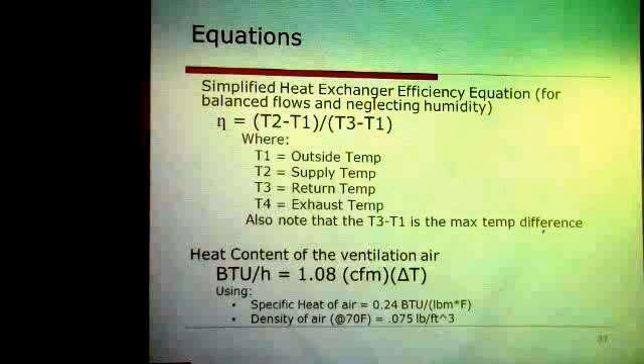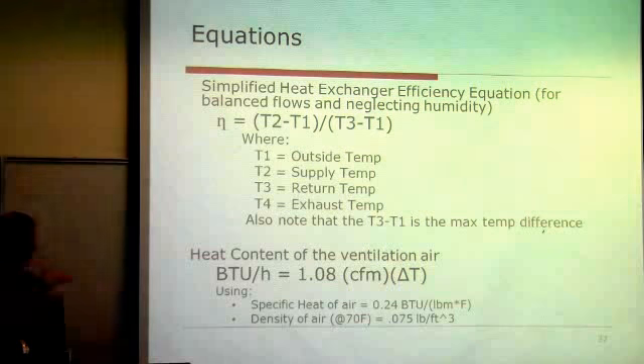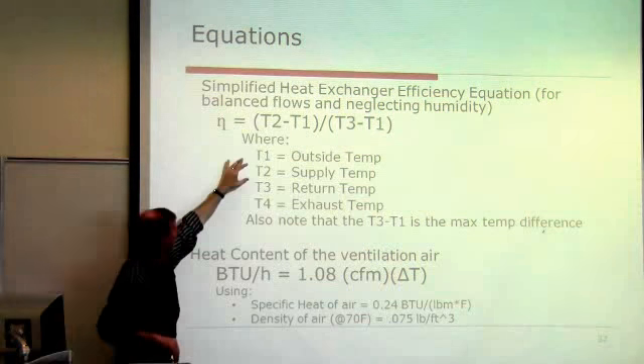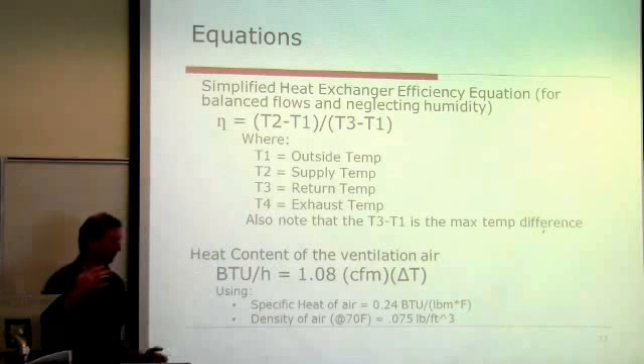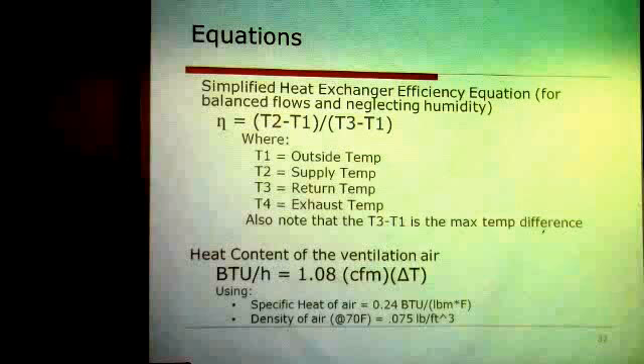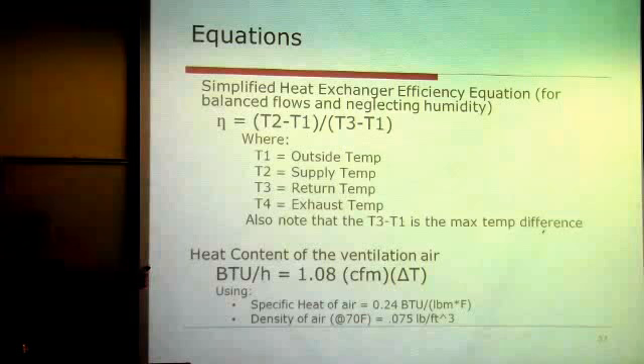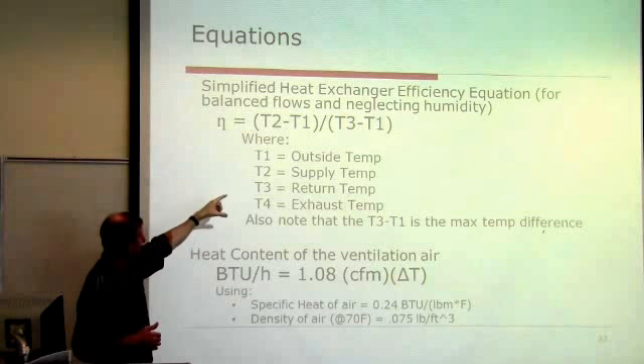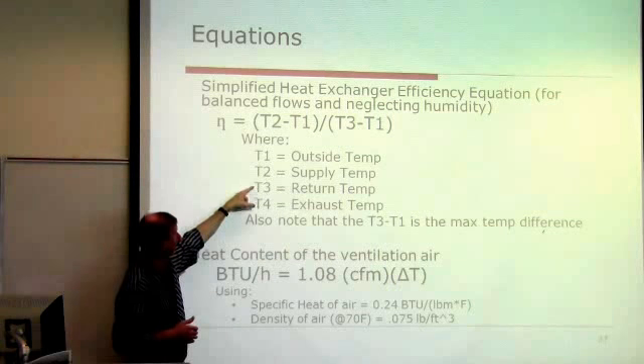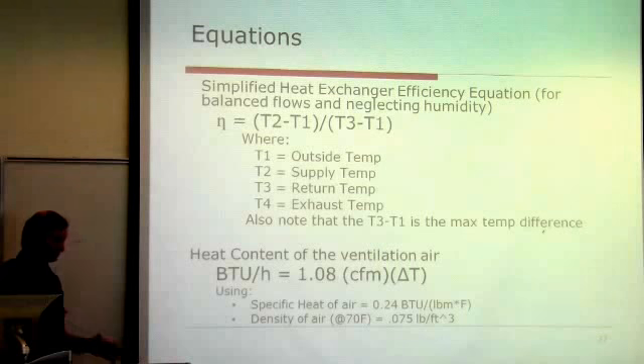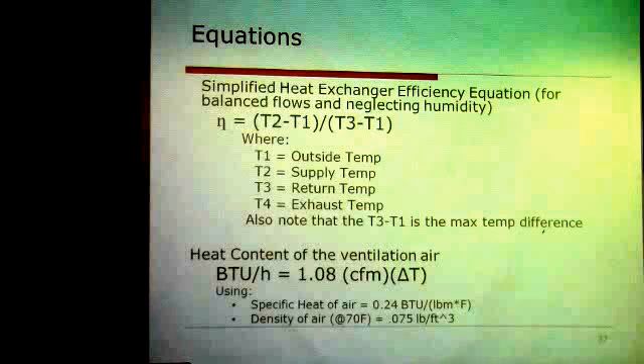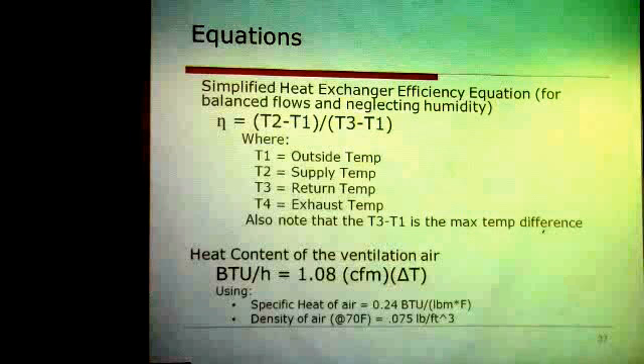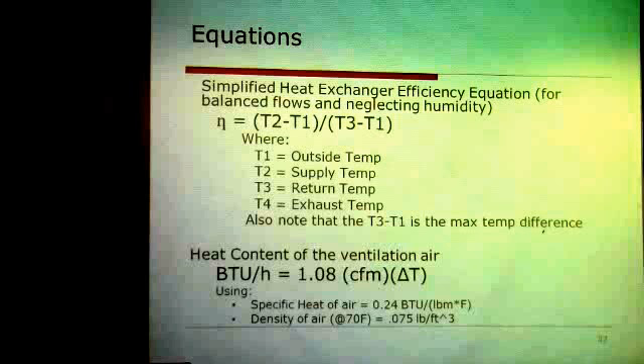How hot did you warm that outside air up to? And that's this one. So say you warmed it up from 40 degrees up to 67. And then you divide that by T3 minus T1. So that's the return temperature minus the outside temperature. So that shows you that's 70 degrees minus 40, so that'd be 30 degrees. So you warmed it up 27 degrees. Am I doing that right?